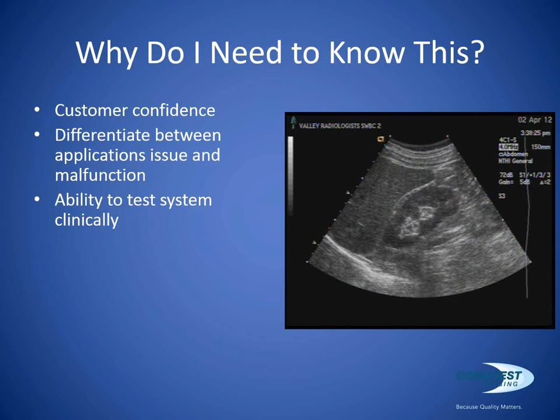The ability to test a system clinically. There's a lot of times where a system will seem operational, it will pass diagnostics, it will power up just fine, but when you actually start scanning, you can pick up noise or image artifacts or things like that. And so the ability to test a system clinically as well as technically makes you a much more complete service engineer.